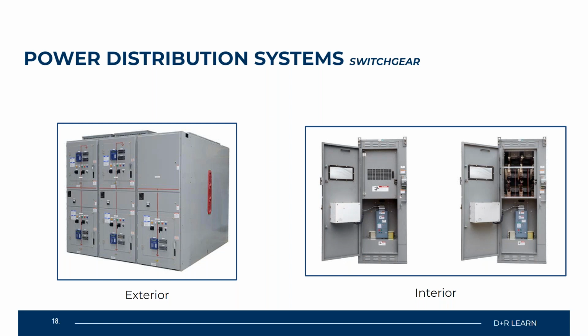Now, switchgear, like I said, is part of the power distribution system, and as part of that system, you will have equipment such as chillers, RTU units, and air handlers. All of these different systems receive electricity through the use of switchgear within the electrical circuit of the system. On our slide here, you can see an image of the exterior and an image of the interior of our switchgear system. On the exterior, a lot of the time, if there is an LCD screen present, you can find the different voltages, amperages, or any other electrical information required, depending upon the manufacturer or vendor which creates these different systems.